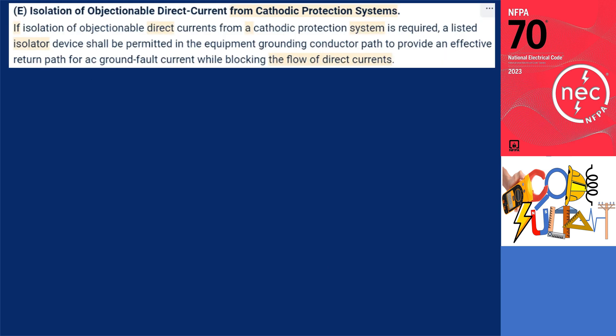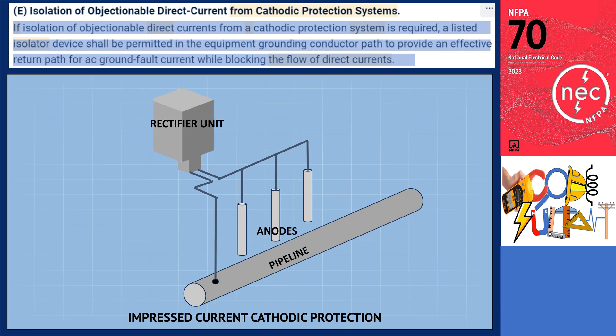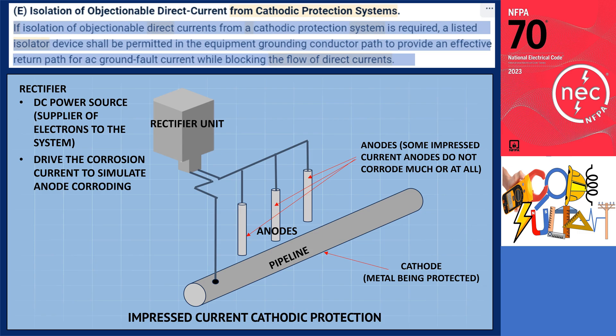Section 250.6E: isolation of objectionable direct current from cathodic protection systems. If isolation of objectionable direct current from cathodic protection systems is required, a listed isolator device shall be permitted in the equipment grounding conductor path to provide an effective return path for AC ground fault current while blocking the flow of DC current. Cathodic protection is a highly effective technique employed to prevent corrosion on metal surfaces. The provided illustration depicts a standard installation of an impressed current cathodic protection system. In this setup, the metal pipe that requires protection is considered the cathode, while the anode, through which current is discharged, is placed within the same electrolyte — typically soil — where the buried pipe is located. Rectifiers of different sizes and motor generator equipment supply electrons to the system and generate the corrosion current, simulating the corroding process that would typically occur at the anode.